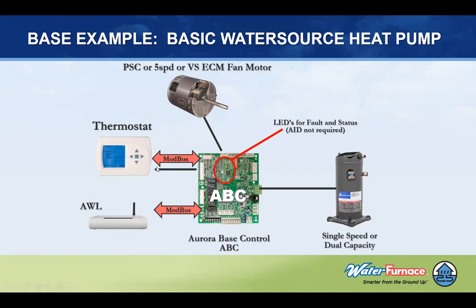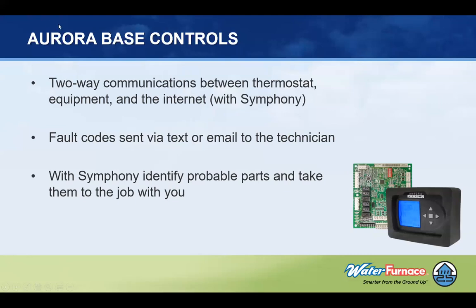And then on a lot of pieces of equipment, this solid line is a hardwired 24-volt connection with the Y1, Y2, W type control. What is added to the WaterFurnace system is a communicating control, which uses a Modbus protocol to a thermostat that then allows us to communicate what the control is seeing out to the thermostat. And then if you connect another Modbus connection to what we call our Aurora Web Link, that connects the Aurora controls to the web and enables Symphony, which gives you remote diagnostics and troubleshooting. So from an Aurora Base Control, you get two-way communication between the thermostat and the equipment, and then to the internet with that AWL and Symphony.